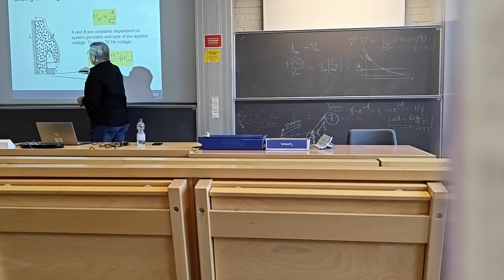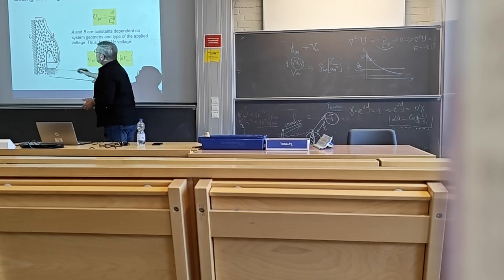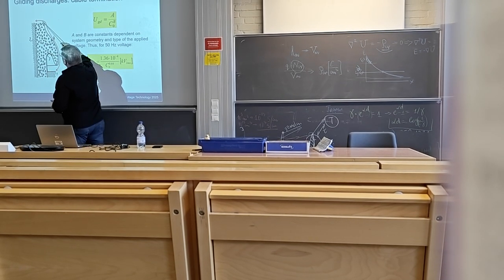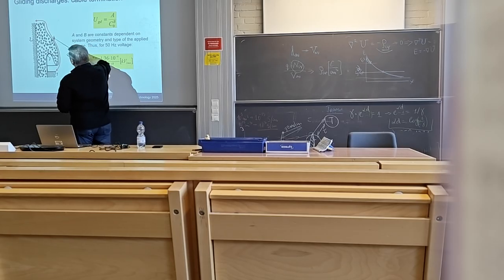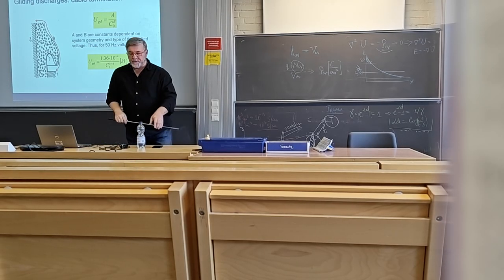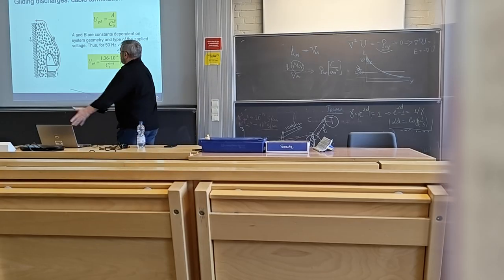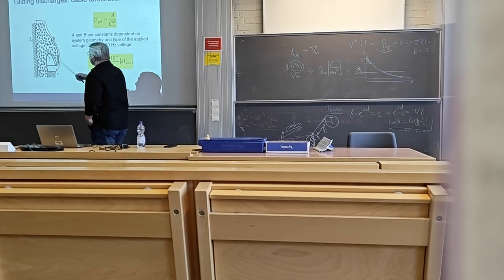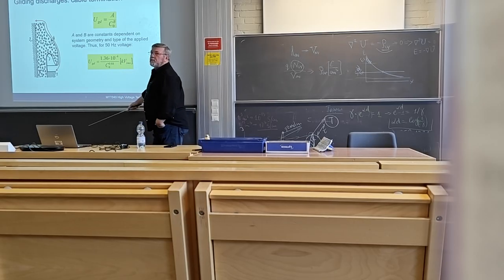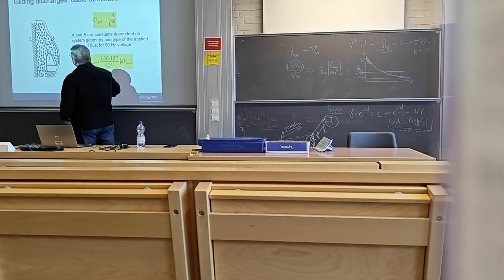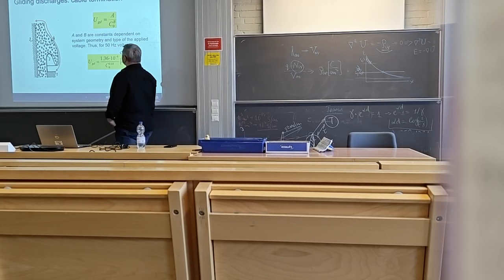So it's a cable termination where we have the stress cone. This is the silicone layer connected to the ground. So typically, this is the conductor here, which is under high potential. So what paths can one expect? Like this, through the surface. There is no way actually to have a breakdown through the gas phase in any other way. So for this one, you need to shape this properly and select the distances and so on.